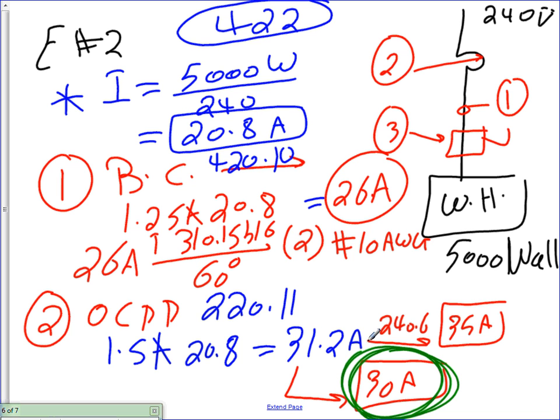So what's the last thing left? Disconnect. Now remember, for the disconnect, if the overcurrent protection device is within 50 feet of the appliance, you don't need a disconnect. If you don't have it, the code doesn't say exactly how to size it, but I size it at exactly 1.25, like a continuous load, for my disconnect.